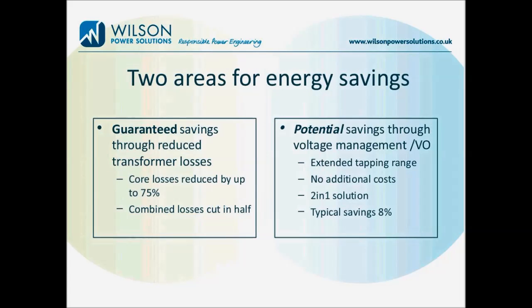But the savings through the reduced transformer losses are not all. In addition to those guaranteed savings we've discussed, as a result of those transformer losses, many customers and clients can realise substantial additional savings through voltage management or voltage optimization, as is known, at no extra cost. What the units are designed to do is deliver the required site voltage, and in addition they come with an extended tapping range as standard.